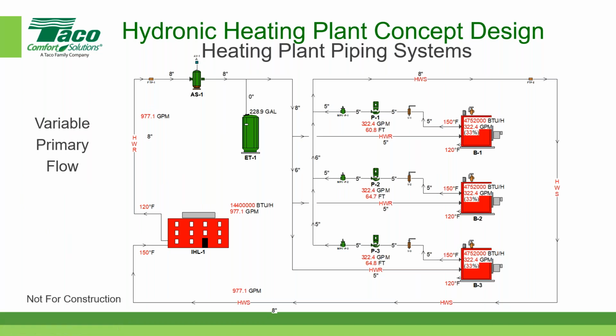Now, in this particular case, I have not shown a bypass, which may be necessary in order to maintain the minimum flow required by the boiler, which is why I put this nice note down here in the lower left-hand corner, Brett: not for construction. I already took a picture and sent it to 6 people that were requesting it. So it's already on the web. So people are already designing the system. This is just for classroom purposes to point out some different configurations of equipment.